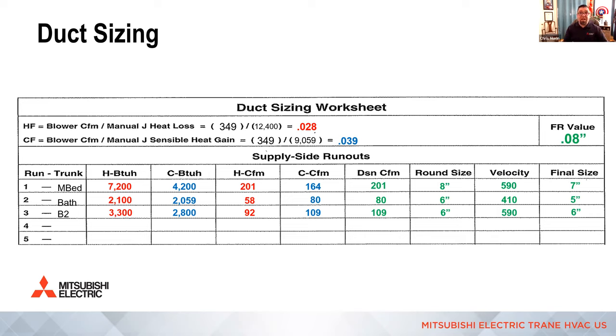Now, of course, with low static air handlers, we don't necessarily have to worry about sizing the trunk in this example. But if we're going to run a large round trunk, we want to size that trunk based on the total design CFM, not the 349 that we actually are running at. We want to design it around, please forgive me, looks like 390, okay? When you add up the green design CFM values. So pretty cut and dry.